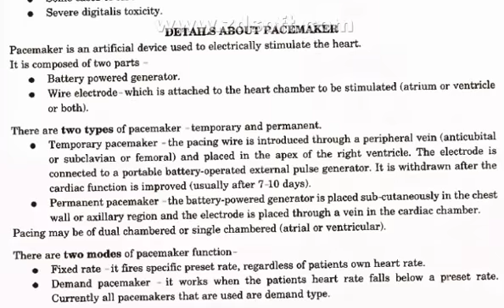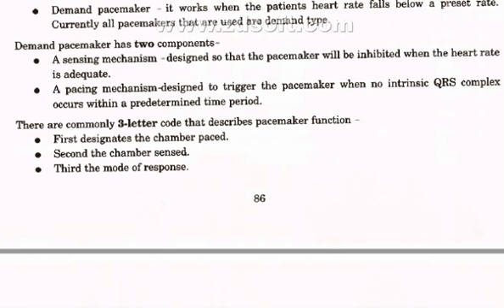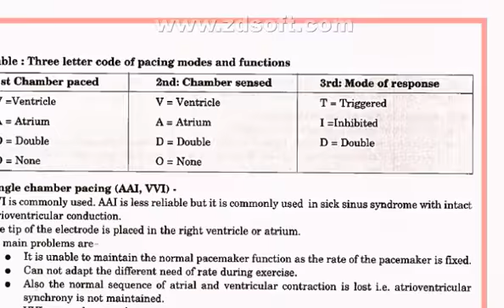Demand pacemaker has two components: a sensing mechanism designed so that the pacemaker will be inhibited when the heart rate is adequate, and a pacing mechanism designed to trigger the pacemaker when no intrinsic QRS complex occurs within a predetermined time period. There is a commonly used three-letter code that describes pacemaker function. First, designates the chamber paced. Second, the chamber sensed. Third, the mode of response. Three-letter code of pacing modes and functions.